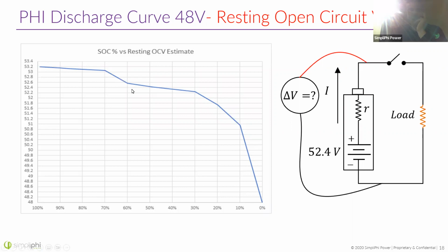We start to get some drop-offs as we get to lower states of charge. At 30% state of charge, you're down to about 52.2 volts, right? And then we get to the end of this discharge cycle, and after you hit about 10%, the voltage drops off really quickly. We call that location the knee. Notice at the top, I've labeled this graph resting open circuit voltage.